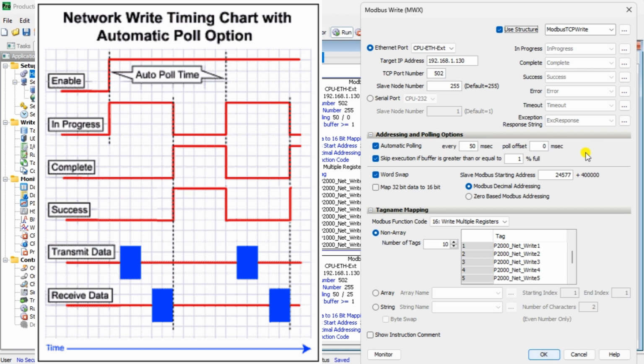The message queue stages the messages from the ladder code to go out to each physical communication port without requiring interlocking logic. The longer the poll time within the application's tolerance, the better the overall network performance. So for efficiency in programming and the best possible performance of the network, conservative poll rates should be used when utilizing the automatic poll feature.